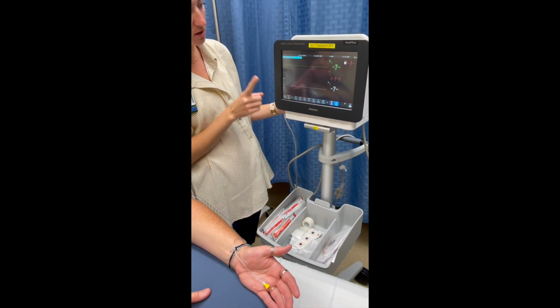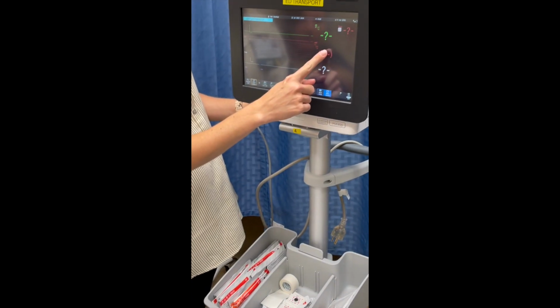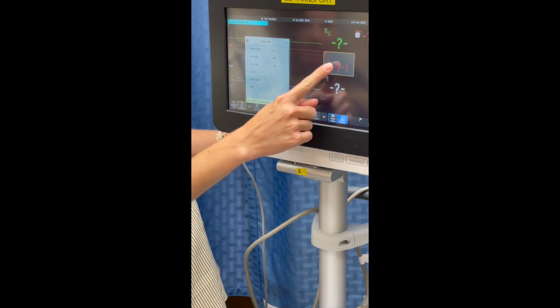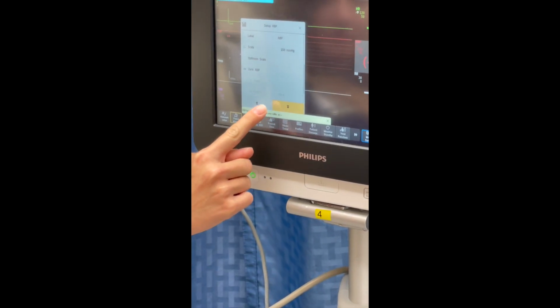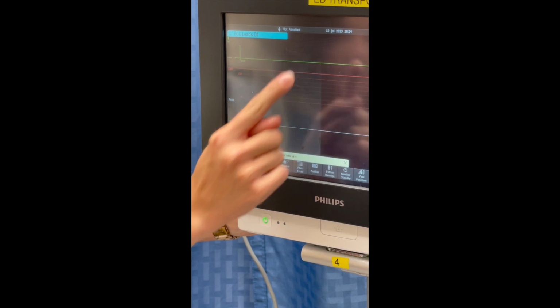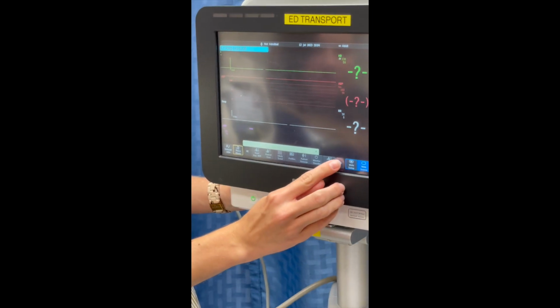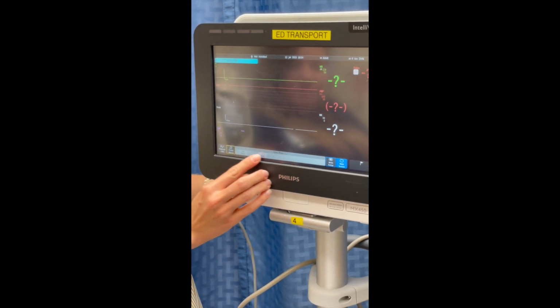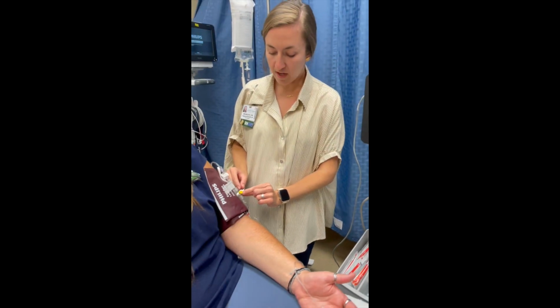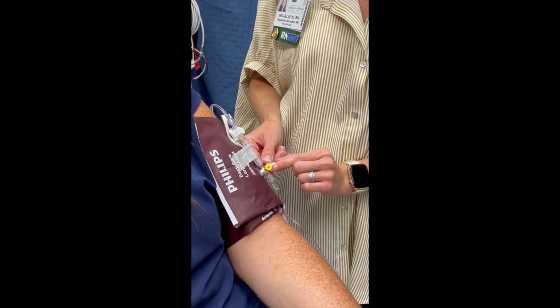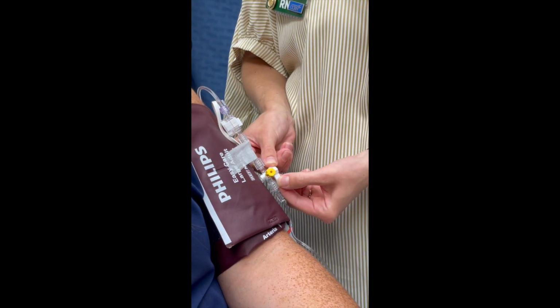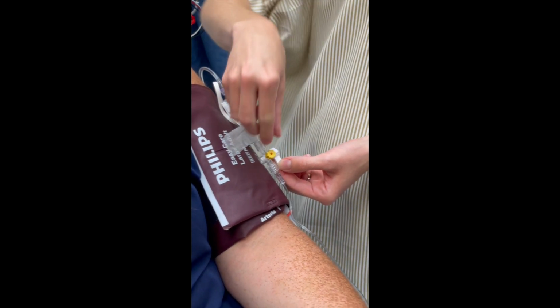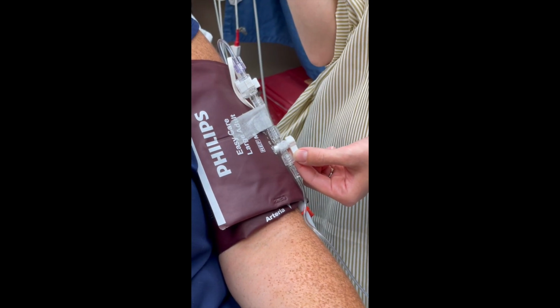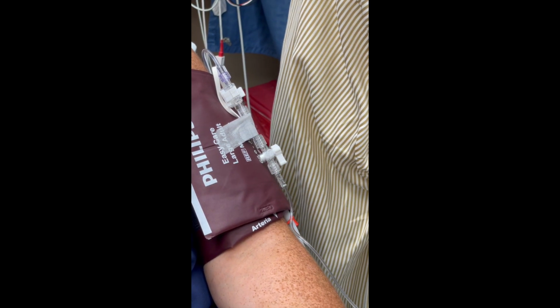On your monitor, there are two ways to find this. Clicking on your waveform here and scrolling down to 0 ABP, or down at the bottom, scrolling over to 0, which will give you options for any pressure cables that you have attached, 0 ABP. We are going to turn the system off to the patient, open to the transducer, open to air, and press 0.